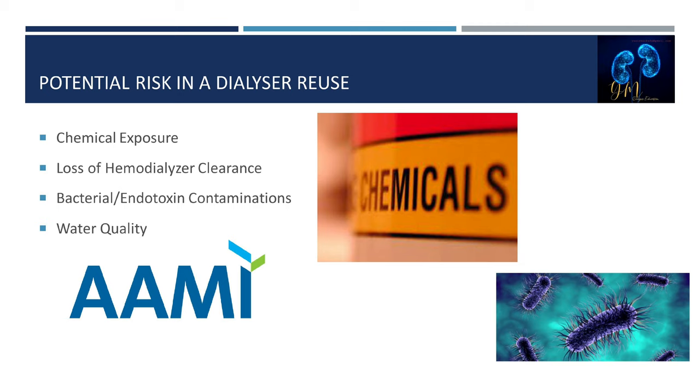Symptoms of a pyrogenic reaction may include fever, chills, nausea, vomiting, or low blood pressure. Muscle pain and symptoms of sepsis — bacteremia in the blood — will cause fever, general malaise, and positive blood culture. Water quality monitoring is essential and required to protect patients. AAMI standards specify that bacteria in dialysis water must not exceed 100 colony-forming units per mL, with an action level of 50 CFU/mL. Endotoxin should be less than 0.25 endotoxin units per mL, with an action level of 0.125 EU/mL.